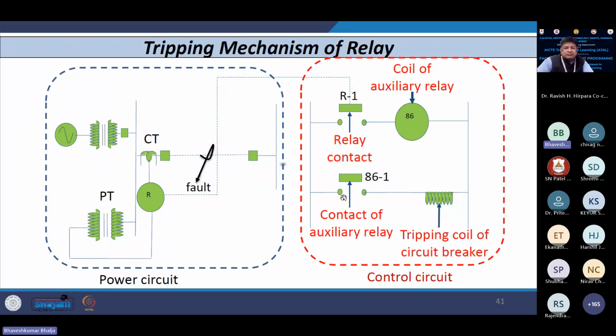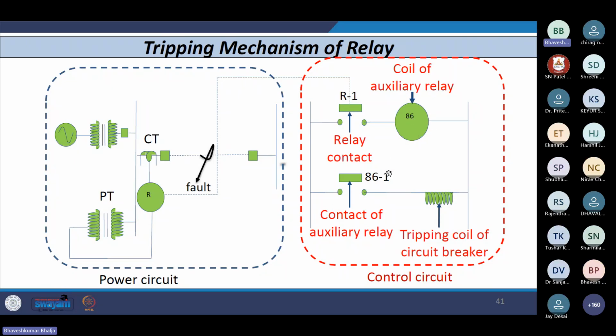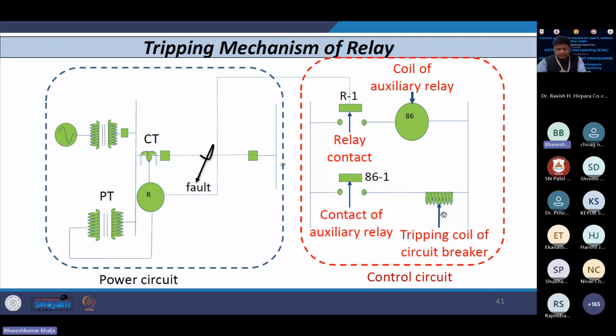So some sensing mechanism is there at some bus level, local or sending end. A similar mechanism is also there at the other end, the receiving end. So your relay is going to sense the fault, and it is going to send a signal to its contact. The contact will further energize the auxiliary relay, and when the auxiliary relay contacts close, the trip coil of the circuit breaker is energized, and this breaker which is here is going to open and the fault can be isolated.